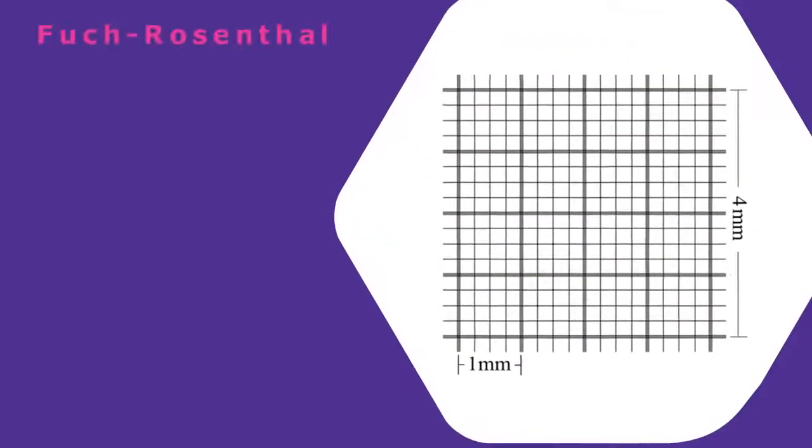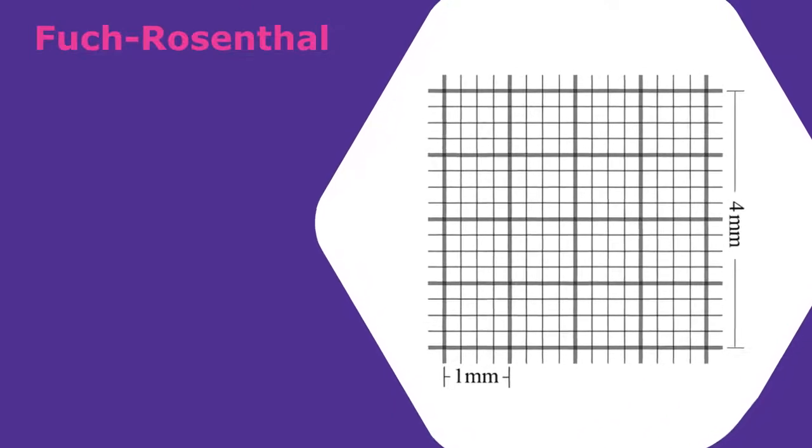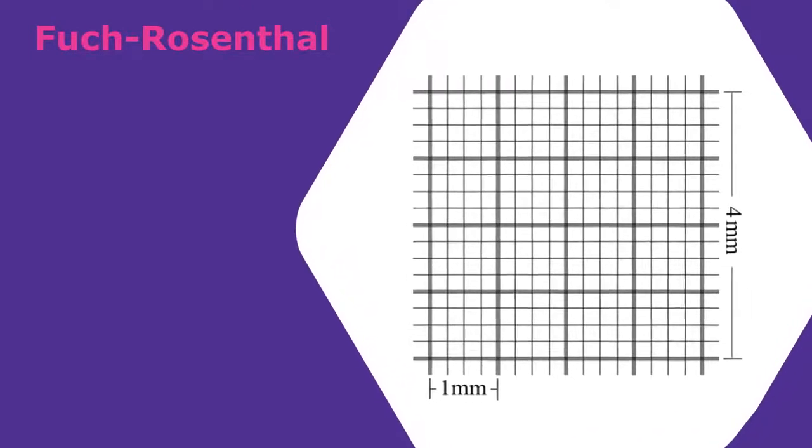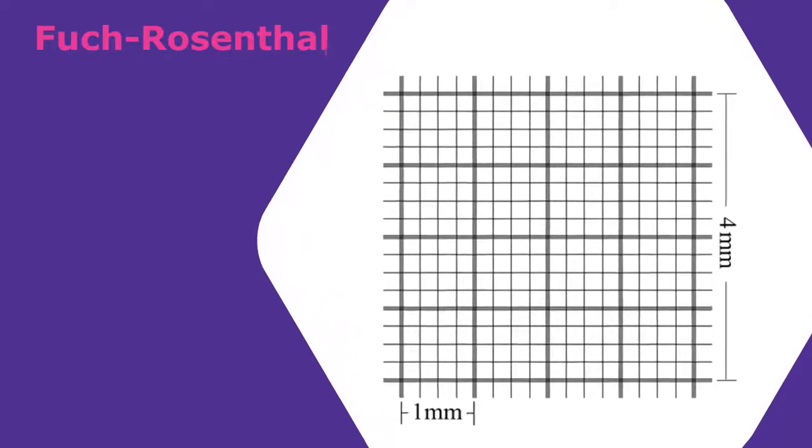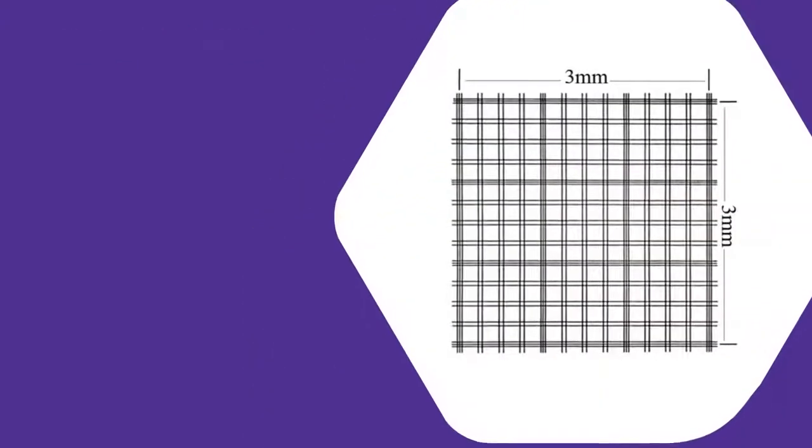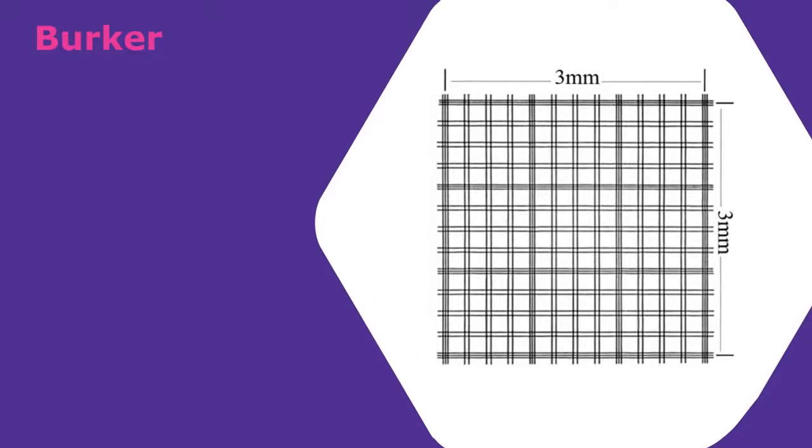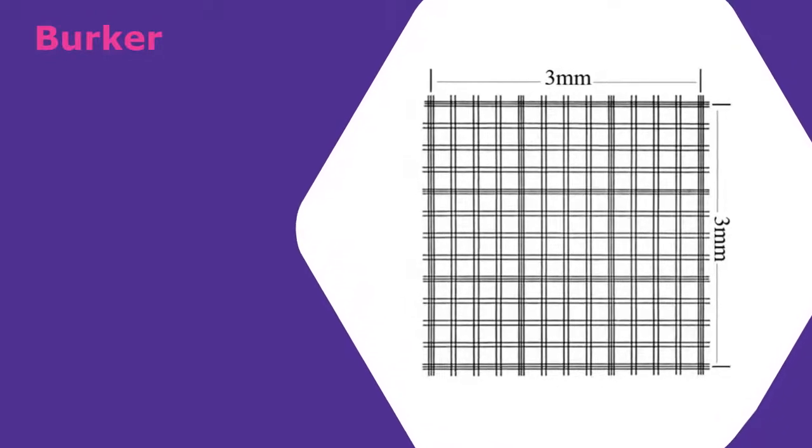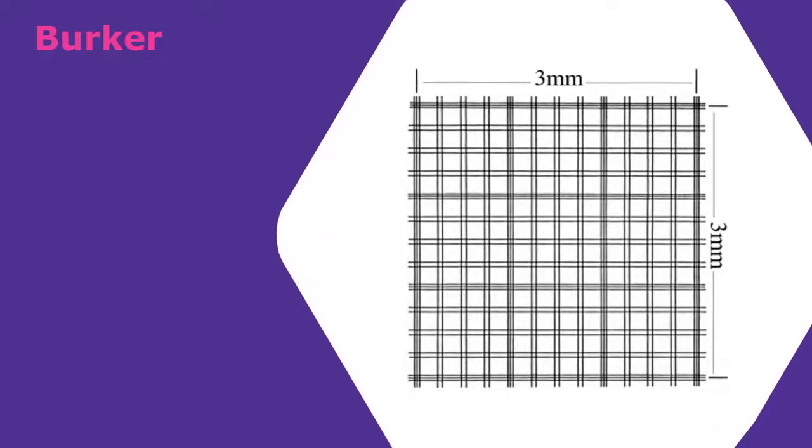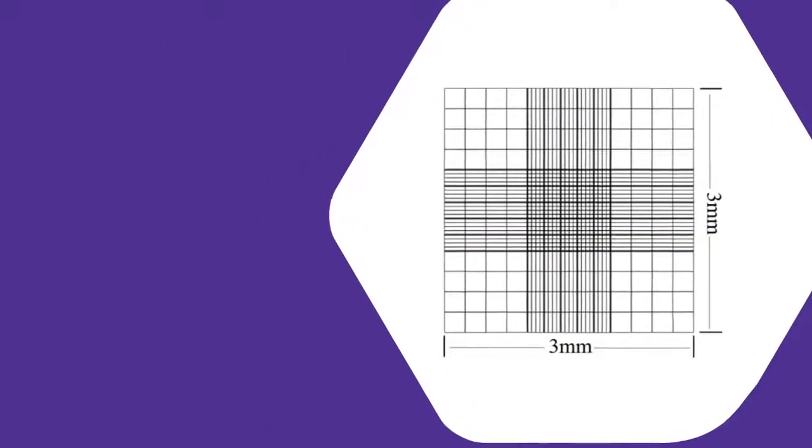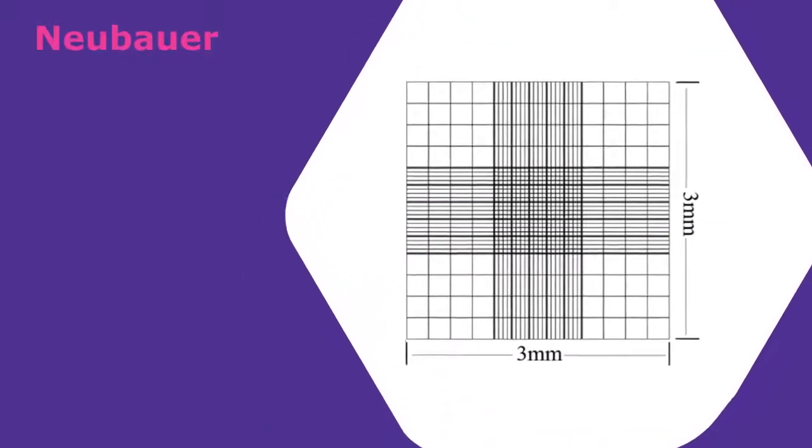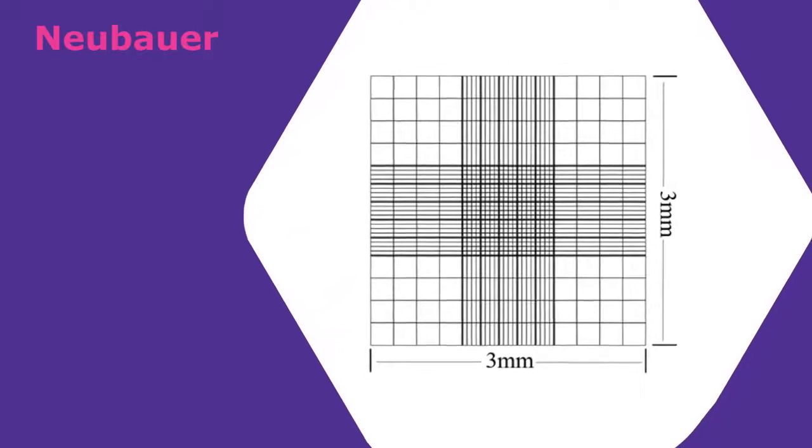Now, you may have encountered various design geometries within the counting chambers and have wondered how they all work. Despite the geometrical differences, all cell counters work under the same principle which takes cell counts at precisely defined nanoliter volumes. So, as long as we know the dimension of the grid and the volume of the chamber, we can calculate the cell concentration.